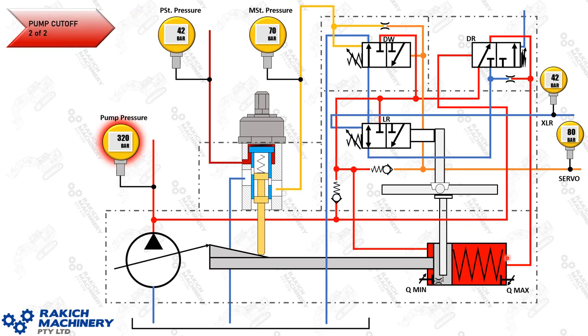Now the pump is pushed back to Q-min, and it will maintain 320 bar all the while there's operator demand. It won't necessarily be on the Q-min stop, but it will be at a point that supplements the leakage to maintain 320 bar — so it might be just off Q-min.